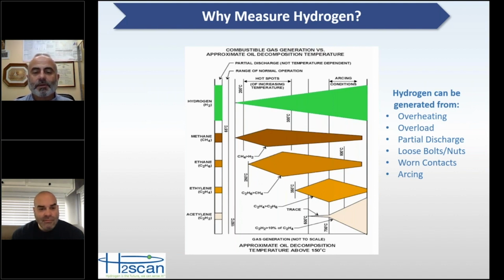As your temperature increases, if you're looking at the other gases in your oil, methane, ethane, and ethylene, your hot metal gases, those will start being generated. And of course, once you have arcing in the transformer, you also get acetylene. And so one of the misconceptions about hydrogen is people will take an oil sample and say, well, I've got these other gases, methane, ethane, maybe even ethylene or acetylene, but I don't see any hydrogen, so I don't think hydrogen is important.